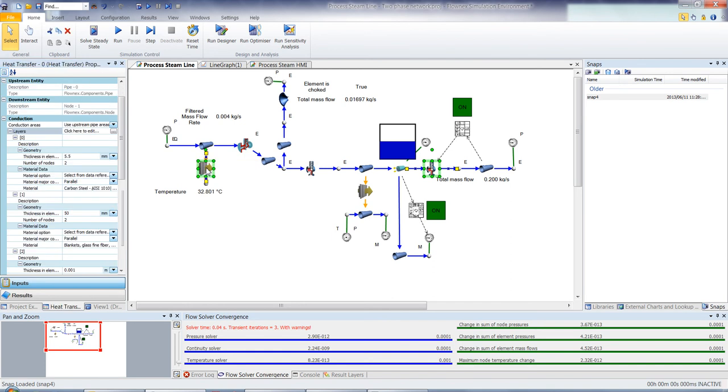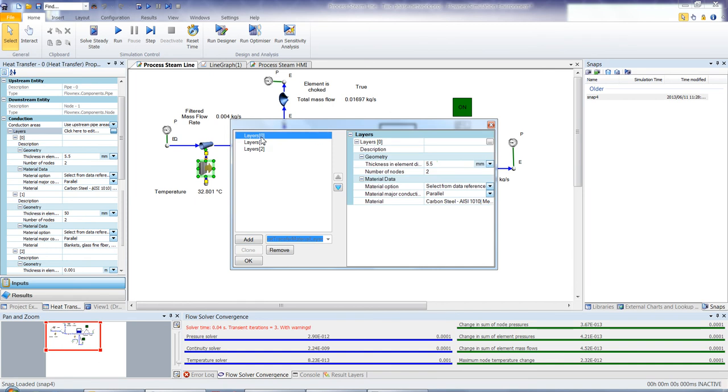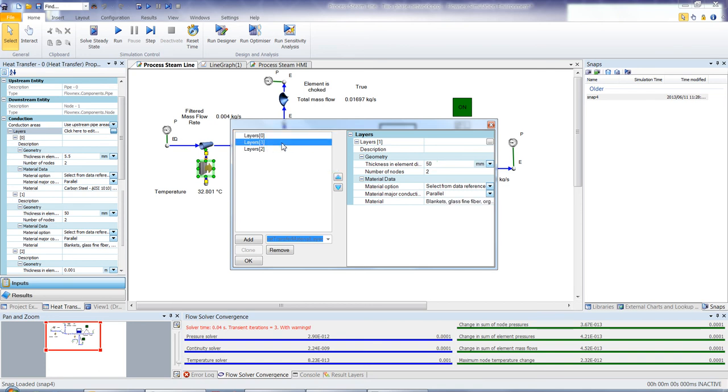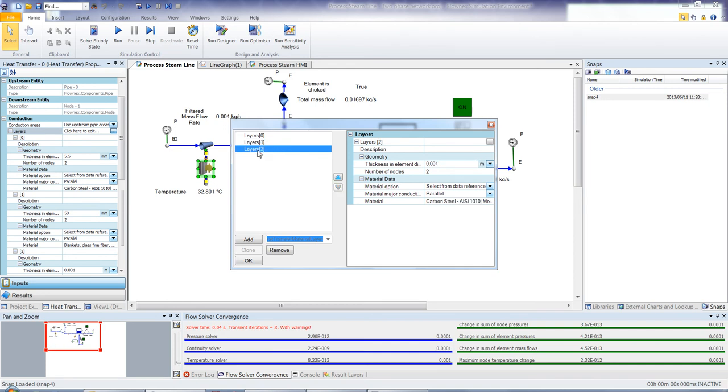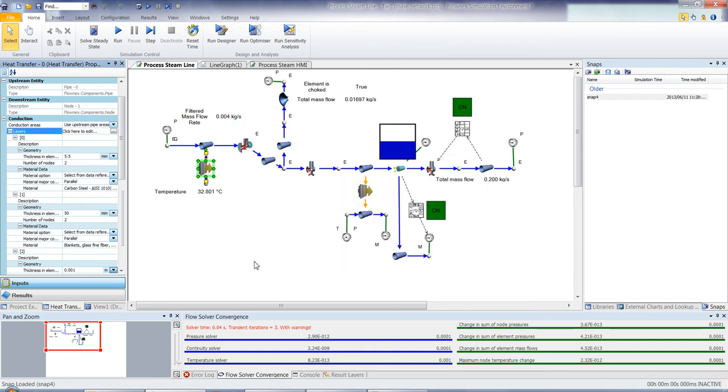So now what I'd like to focus on is the heat transfer and the ability of Flownex to model insulation layers. So that's conduction. And we're going to look at the specific conduction layers, which we have modeled in this case, where we have an initial layer of carbon steel at around 5.5 millimeters, which is our pipe thickness. We're then modeling an insulation layer, which is a fiberglass blanket, and that's at around 50 millimeters. And then our final layer is a thin layer of carbon steel cladding on top of the pipe. So what's quite important to us in this type of simulation would be to ensure that our surface temperature is within an acceptable range, only if we design that insulation thickness to be at an accurate size.